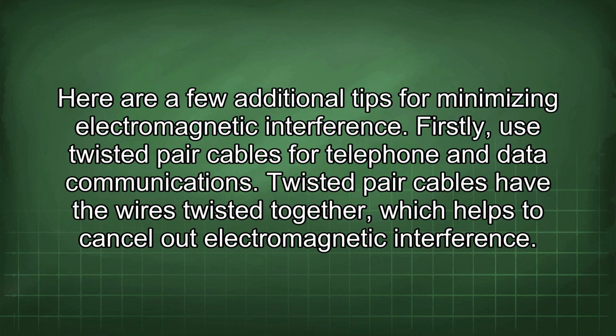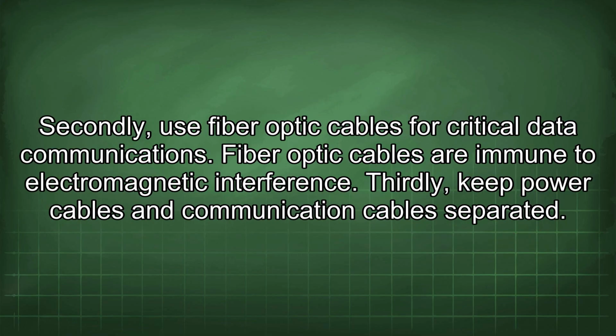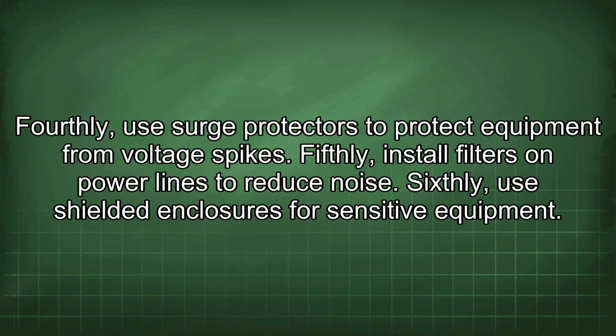It may be necessary to experiment with different shielding techniques, grounding methods, and equipment configurations to find a solution that works. Here are a few additional tips for minimizing electromagnetic interference. Firstly, use twisted pair cables for telephone and data communications. Twisted pair cables have the wires twisted together, which helps to cancel out electromagnetic interference. Secondly, use fiber optic cables for critical data communications. Fiber optic cables are immune to electromagnetic interference. Thirdly, keep power cables and communication cables separated. Fourthly, use surge protectors to protect equipment from voltage spikes. Fifthly, install filters on power lines to reduce noise.